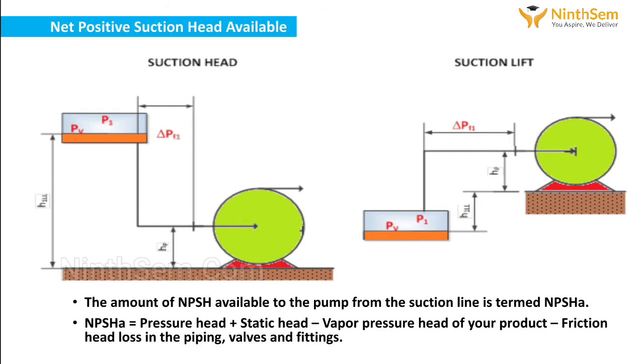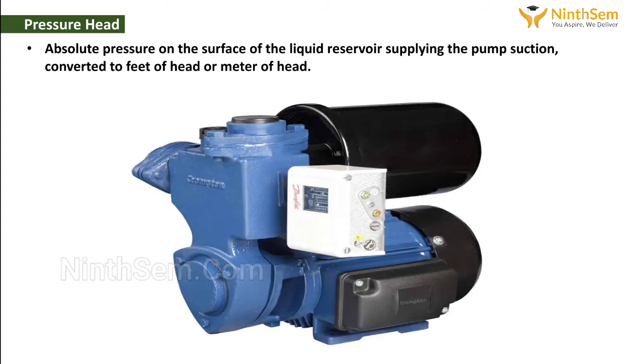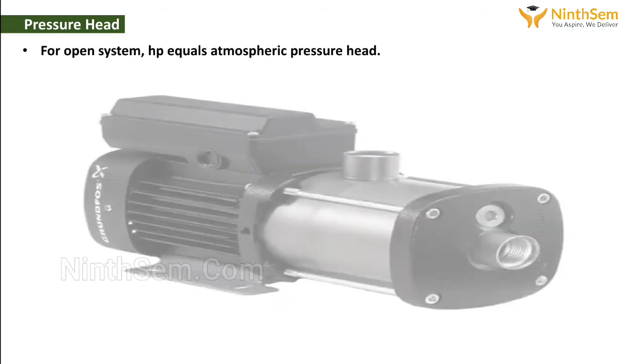So let's come to pressure head. What is a pressure head, which is also termed as HP? Pressure head refers to absolute pressure on the surface of the liquid reservoir supplying the pump suction, which is converted to feet of head or meter of head. If the system is open, pressure head equals atmospheric pressure head.